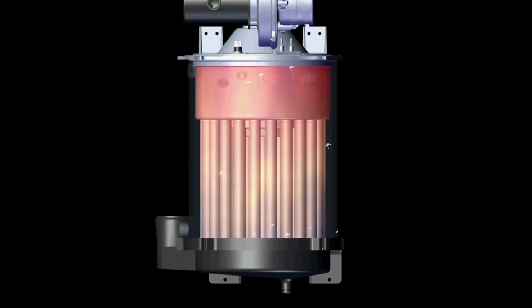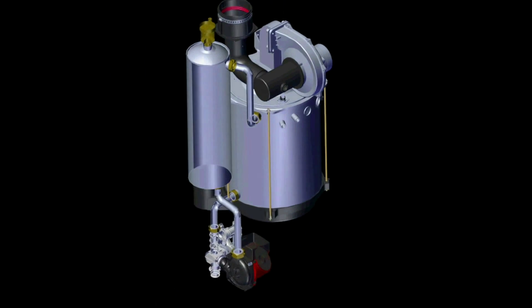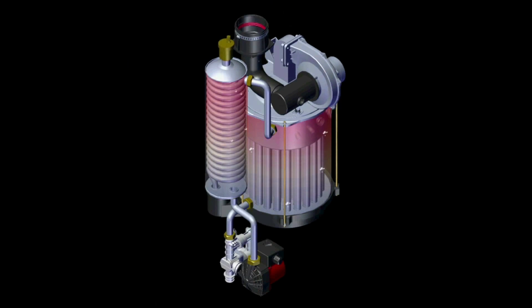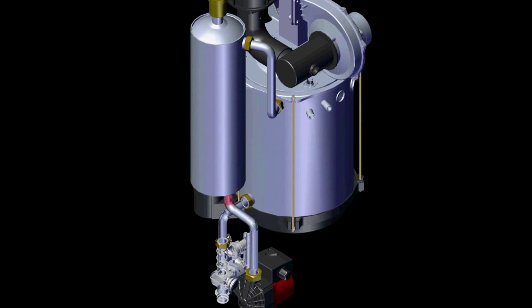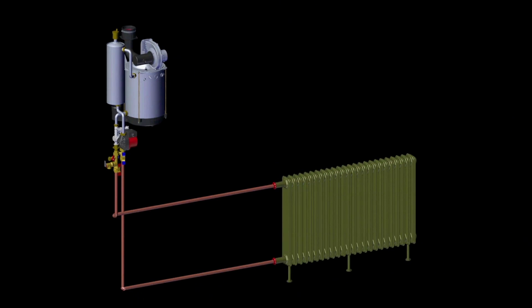Heat is exchanged rapidly through the highly efficient heat exchanger, transferring energy quickly to heat the system returned water. The internal central heating circulation pump will operate and circulate the heated water through the boiler heat exchanger and internal storage tank. When there is a call for heat, the primary central heating circulation pump operates. The three-way diverting valve directs the heated hot water supply to the radiator or baseboard to heat the house rapidly. Once this heated water passes through the radiator or baseboard, the energy is released into the room and the cooled water is circulated back to be reheated inside the boiler.